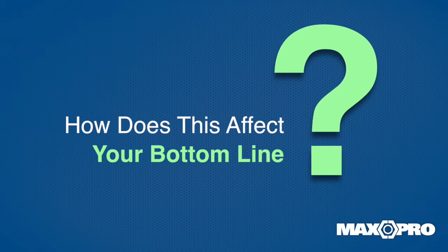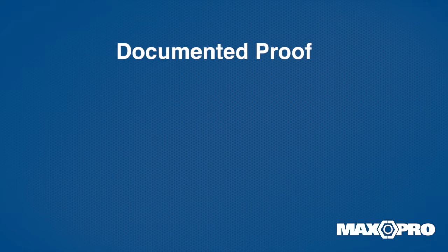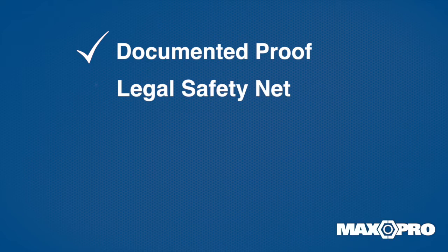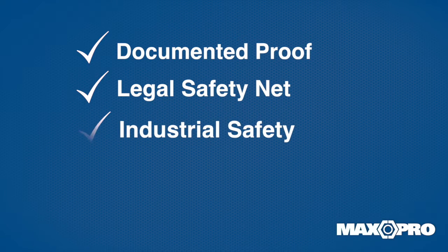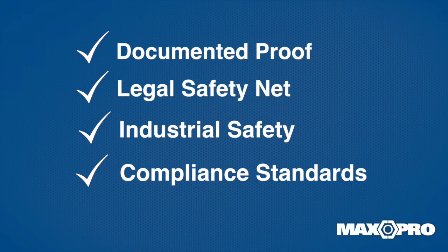How does this equate to your bottom line when using your torque equipment? Documented proof that your equipment is calibrated properly. A legal safety net that can be utilized to ensure that the proper torque tool was used. Industrial safety. You or your employees know that the tool is safe to use. Compliance to meet your quality system standards, ISO, government, or military.